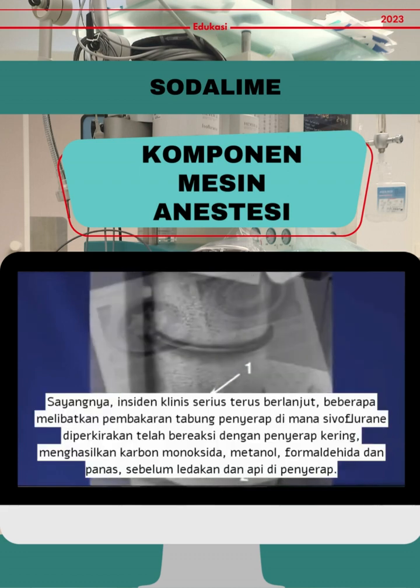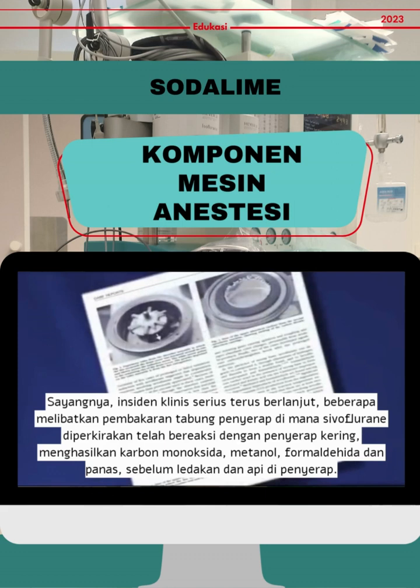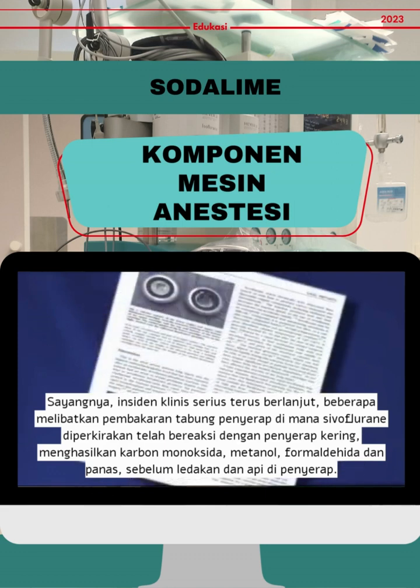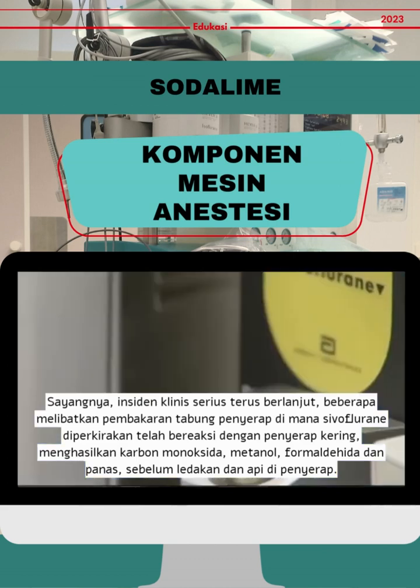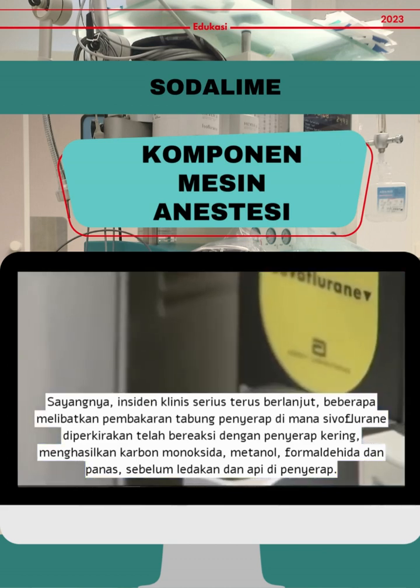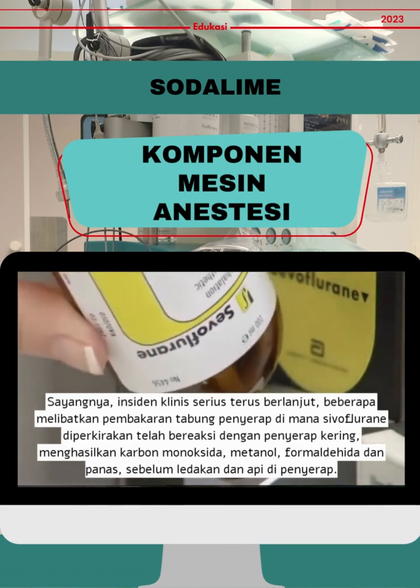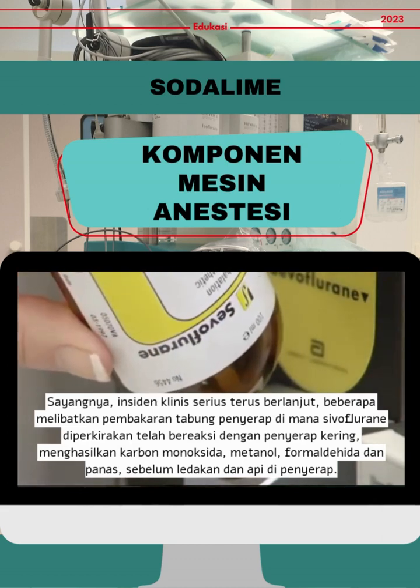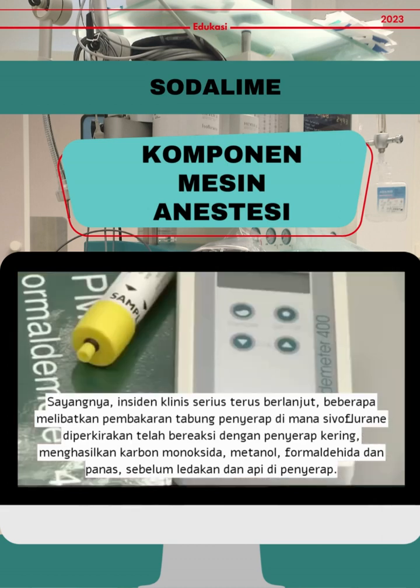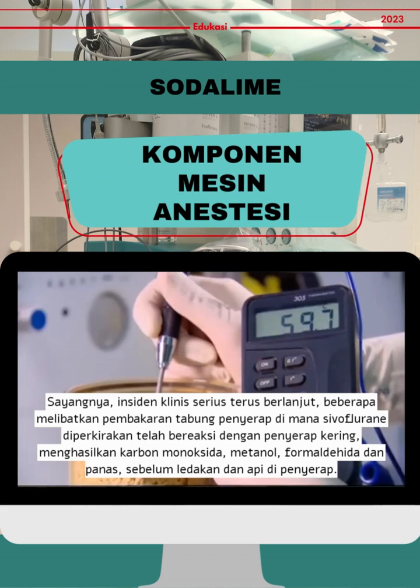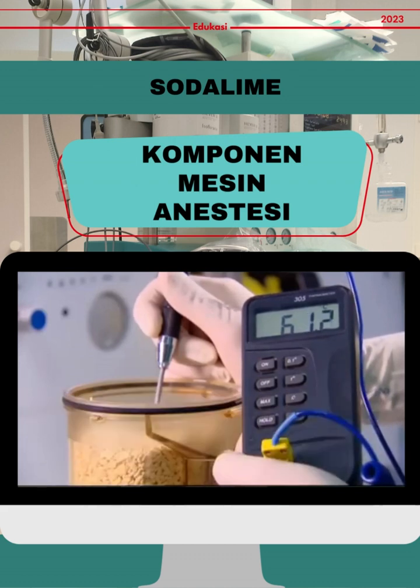Regrettably, serious clinical incidents continued, some involving combustion of absorber canisters, in which sevoflurane is thought to have reacted with desiccated absorbent, producing carbon monoxide, methanol, formaldehyde, and heat, preceding explosion and fire in the absorber.